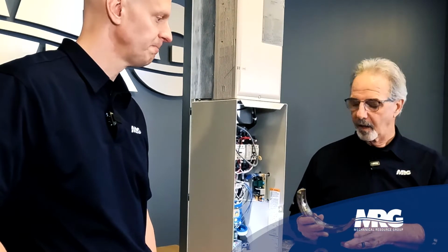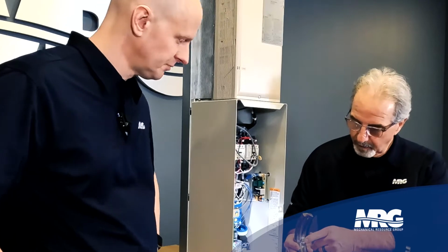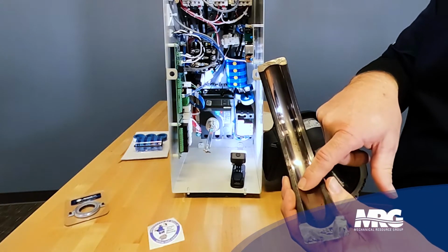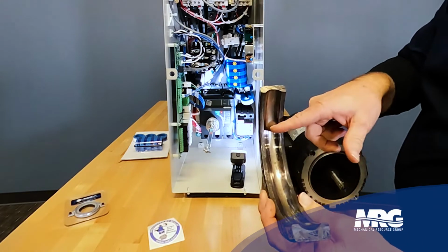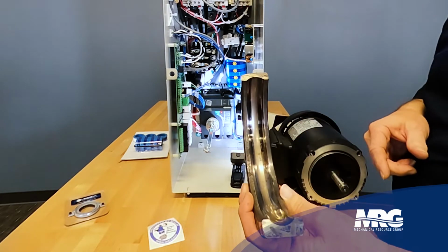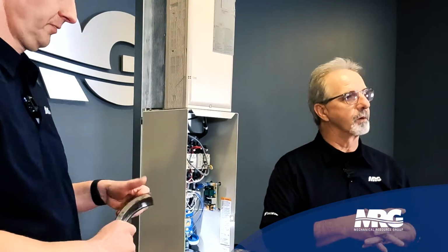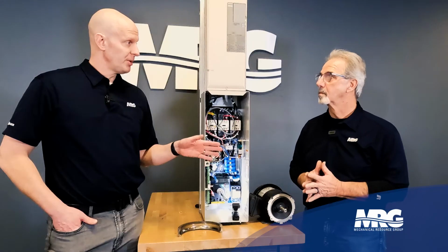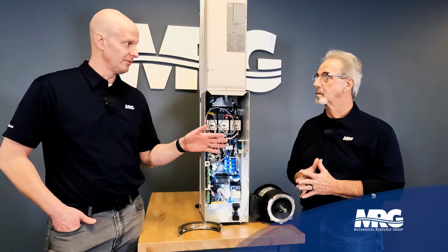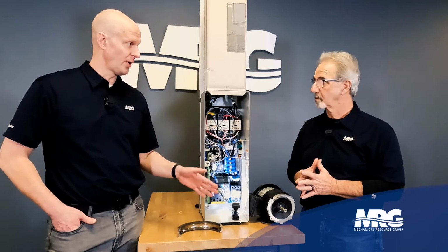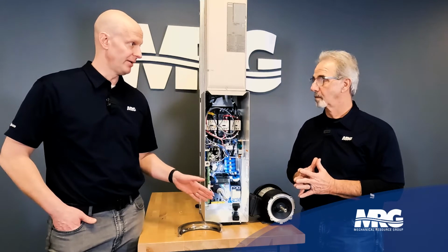Okay, I got you. If you take a look a little bit closer, you can see this pattern beginning to develop, right down through the center where the bearings are running. What happens is it causes the ball to run over a rough surface, the ball gets hot and begins to expand, and the bearing fails prematurely. So in layman's terms, electric current finds a ground, and the ground is through the ball bearing to the bearing ring. Correct.